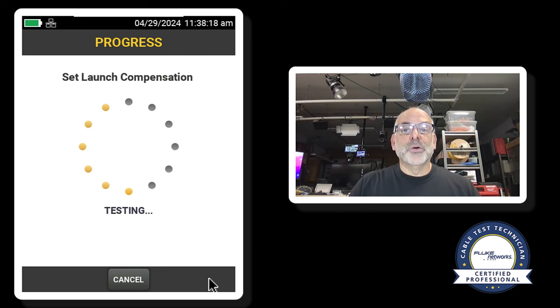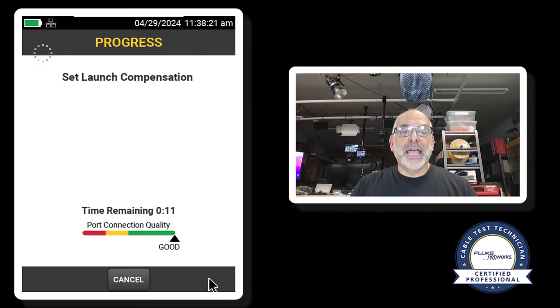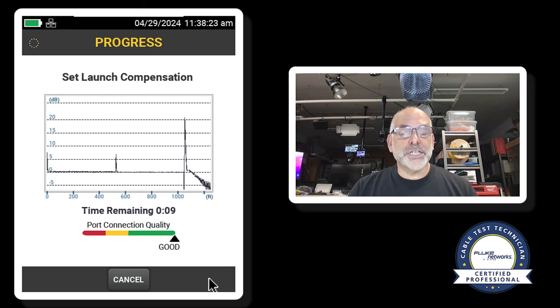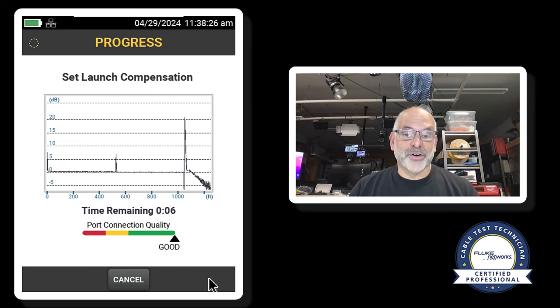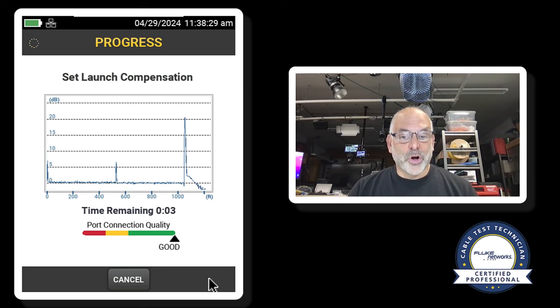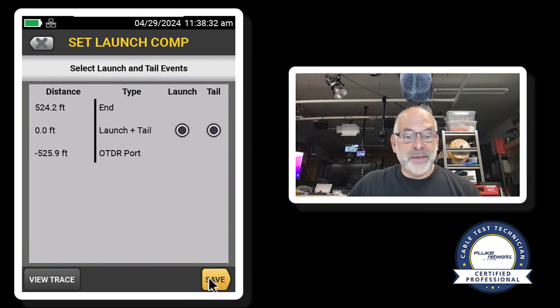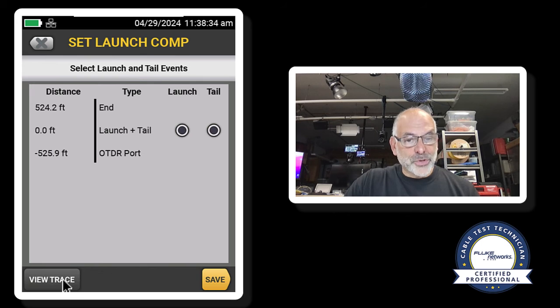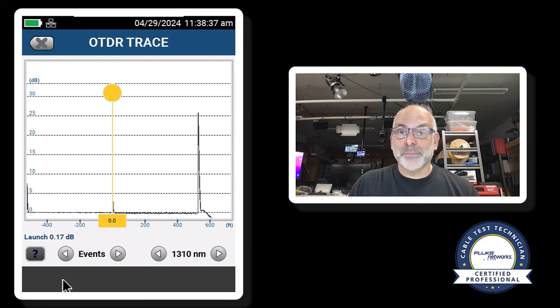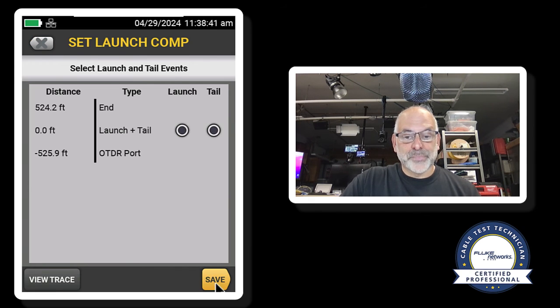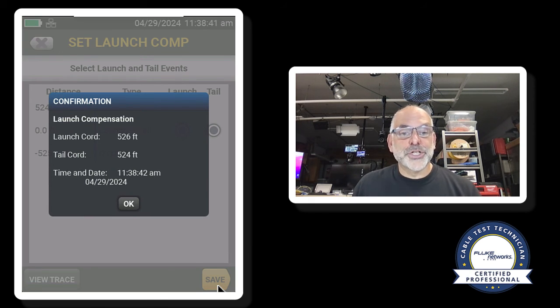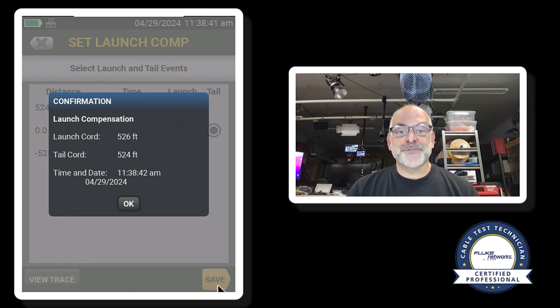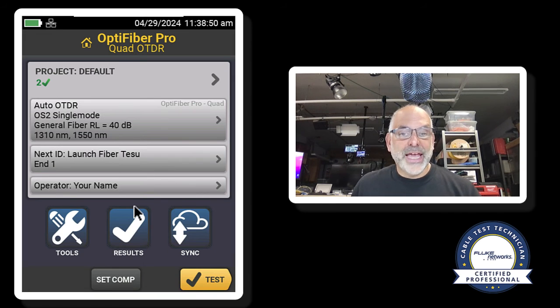So it is running that same test again. And it's measuring the loss and the length of my launch and tail fibers. So we'll see that we're almost done. And it came back. I could view the trace here. I would expect to see pretty much the same number that I saw when I ran the test. I'll go back and I'll hit save. It shows me that my launch fiber is 526 feet long. My tail fiber is 524. I'll go ahead and hit OK.